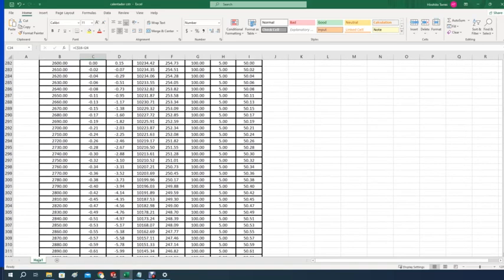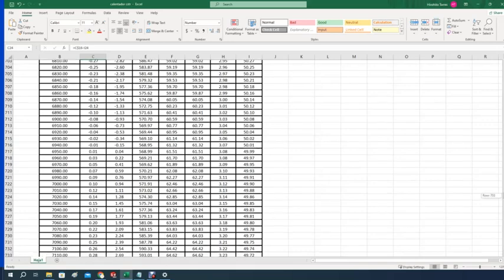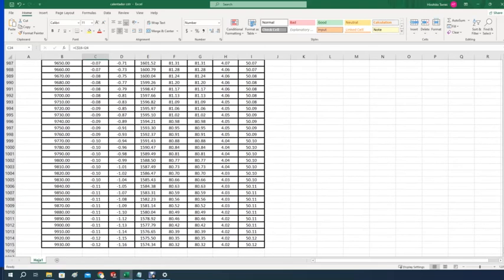So the temperature will go up to 51, 1 degree above, 2 now. And it's not reacting. You can see the number is dropping, but it's not dropping fast enough, because it's saturated. Eventually it hit the 54, well no, actually 53. That seems to be the highest number. Now it's dropping, getting smaller. Now it went down, so it's sort of oscillating. That's what's happening with the values I have right now of tau I around 500 and Kc about 10, causing some oscillation, and eventually it will get back to 50.12.